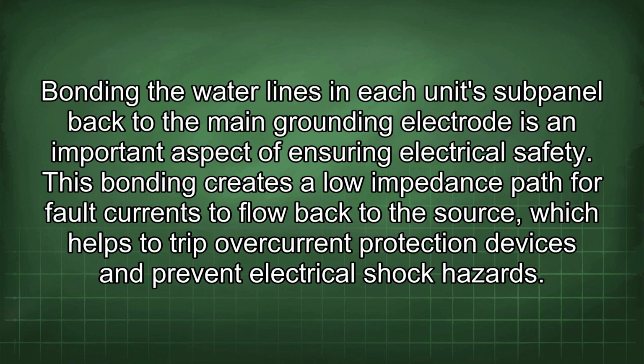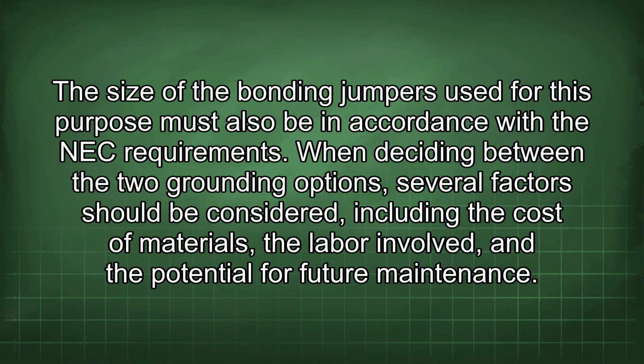Bonding the water lines in each unit subpanel back to the main grounding electrode is an important aspect of ensuring electrical safety. This bonding creates a low impedance path for fault currents to flow back to the source, which helps to trip overcurrent protection devices and prevent electrical shock hazards. The size of the bonding jumpers used for this purpose must also be in accordance with the NEC requirements.